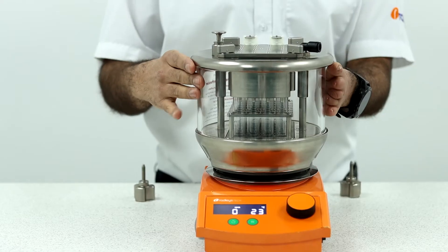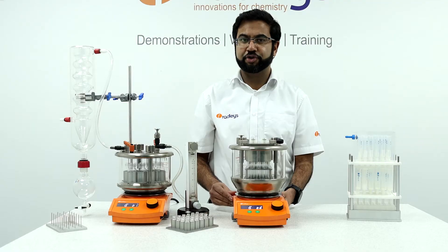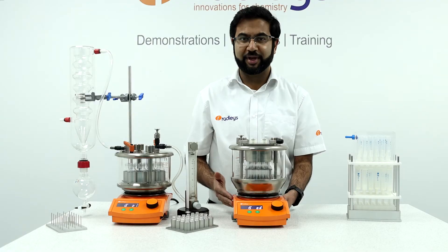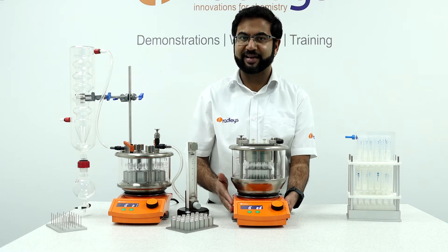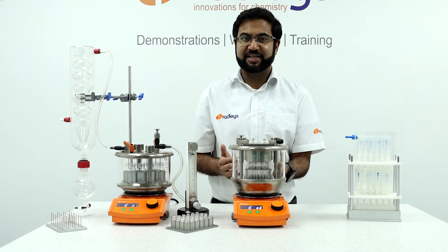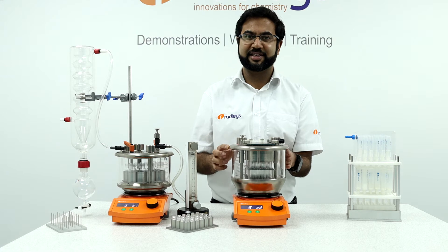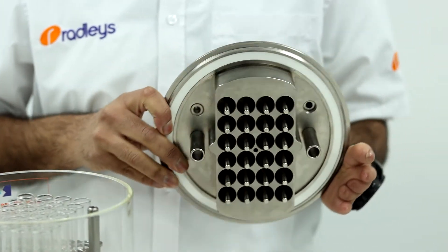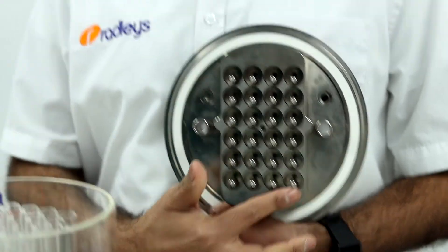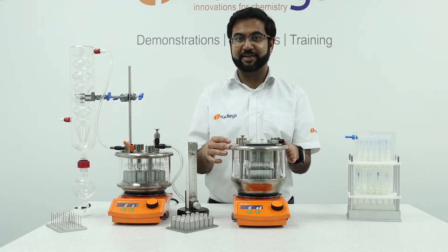With the Greenhouse synthesizer, we have the ability to perform reactions on smaller tubes. You can use up to 24 tubes in a 4x6 format. We have heating and stirring from a magnetic stirrer hot plate. The whole glass chamber is under an inert atmosphere through a gas inlet. The refluxing is now different as you have a cooled head with metal pins — these act as cold fingers to help condensate your vapours. The volume goes from 0.5 millilitres up to 7 millilitres.